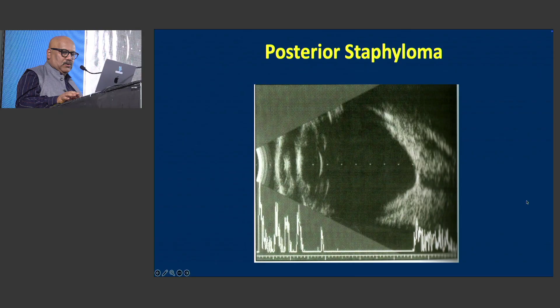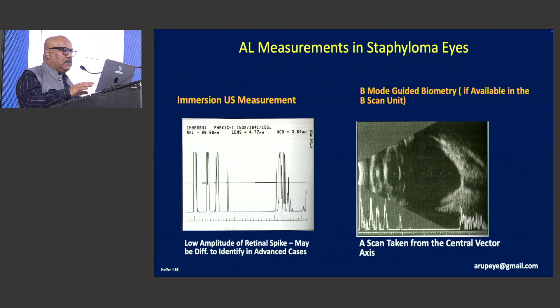Because of staphyloma, if you measure the anatomical axial length, you're going to measure a falsely long axial length. That can be overcome by using the A scan, which is taken from the central vector axis of the B scan. So your A and B scan machine should be able to tell you where exactly the fovea is and then take the axial length measurement there. That is when you're doing an ultrasound biometry, immersion technique.